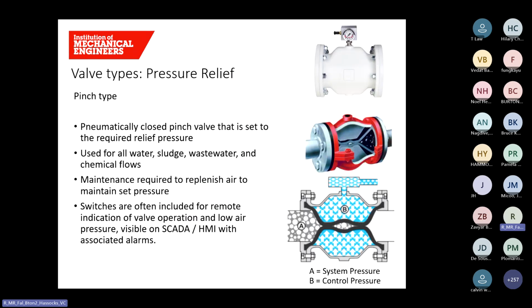A pinch-type pressure relief valve uses a flexible elastomeric sleeve to control and relieve excess pressure in a system. The valve remains closed under pneumatic pressure and set to the required relief pressure. These valves are suitable for use across water, sludge, wastewater, and chemical applications. Over time, air pressure can drop due to minor leaks and aging seals. Therefore, maintenance required to replenish air is critical. Switches are commonly integrated to provide remote status of valve operation and low air pressure, with visibility and alarms through SCADA or HMI systems.